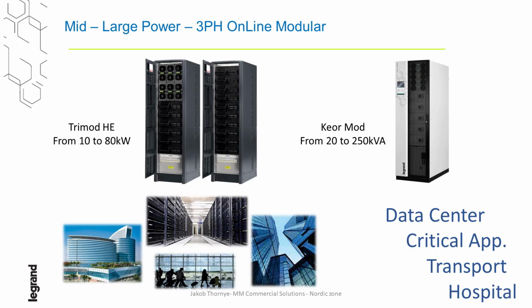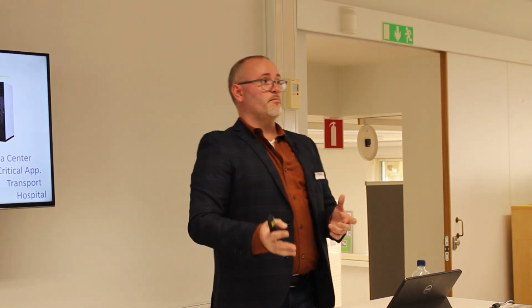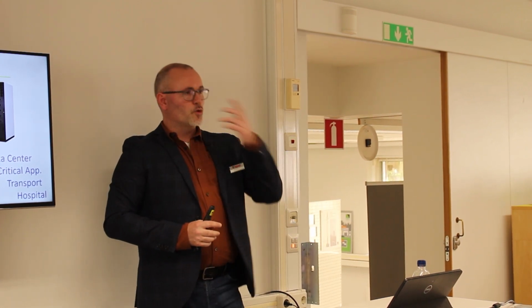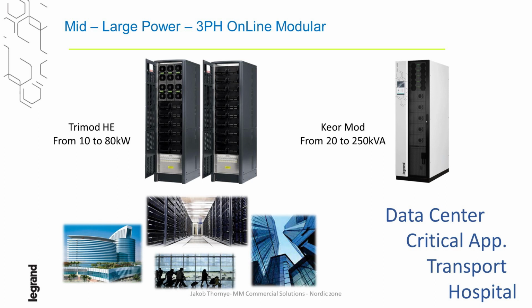Now we start coming to modular. Modular UPS gives different accessibility and makes sure there's no downtime under service, and in case of anything in the installation - a bad battery, a bad faulty power module, a short circuit, or an upgrade - it is much easier to do service and maintenance on a modular setup. As mentioned earlier, investing in modular UPS from the beginning gives you the possibility to increase the flexibility in the installation along the road.